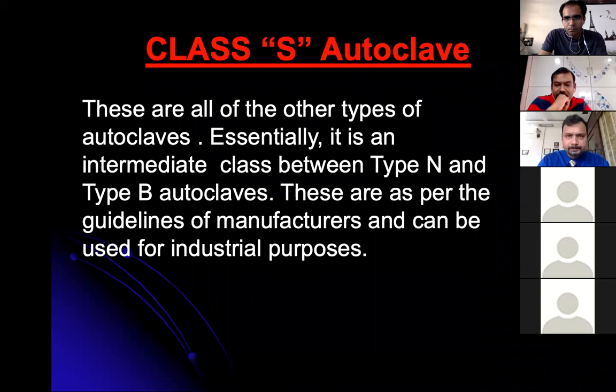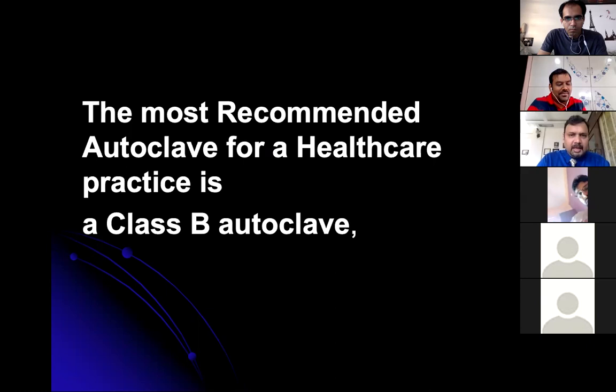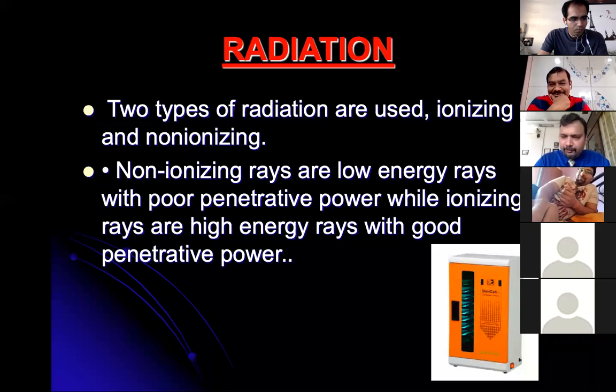Class S autoclave is a combination of N and B types, mainly for industrial use with large loads. In dentistry and healthcare, Class B autoclave is considered the most important and recommended option.